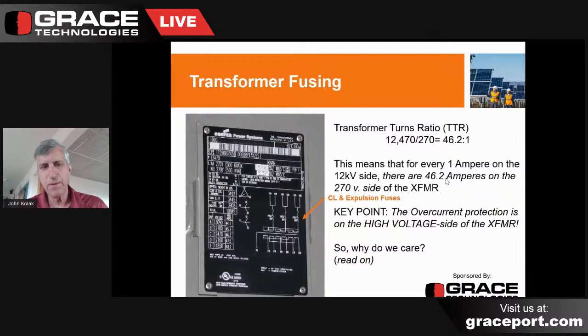I'm sorry, I broke down. My high voltage winding is wound delta, and if you took the time to look at the low voltage windings, they are wound Y. Now, you'll notice that they actually have the fusing illustrated in the actual graphic, the schematic that you see on the nameplate. For example, you see the feed-through bushings we talked about earlier, H1A and H1B feed-through.